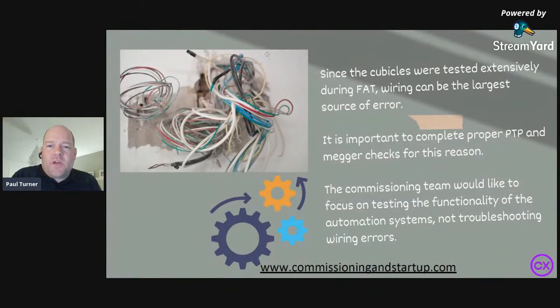Once you get through construction, really the focus, because the hardware and the software were tested extensively during FAT, is really the installation that you're going to be verifying on site. That's largely consisting of all the cables that have been pulled to interconnect all the systems.